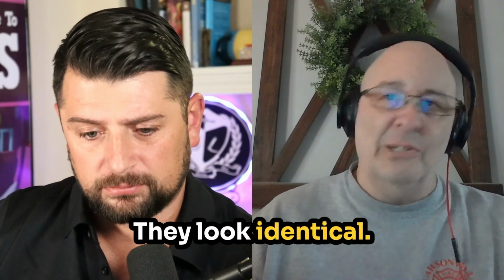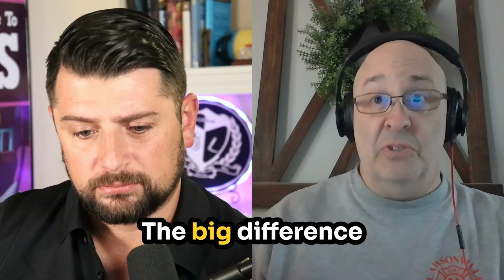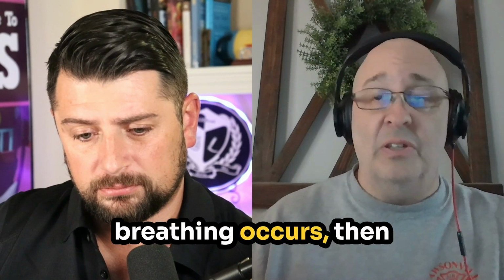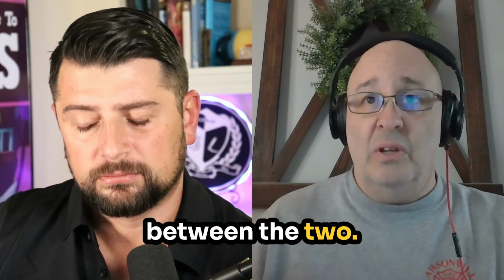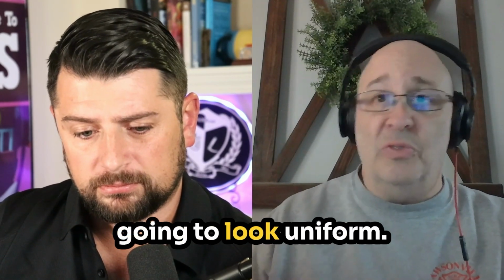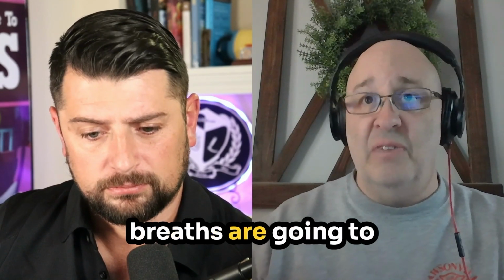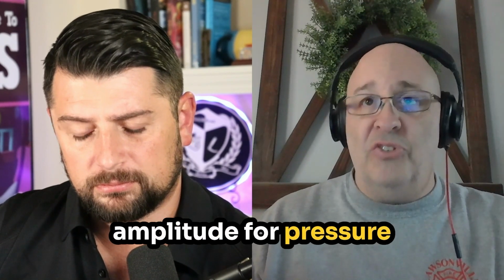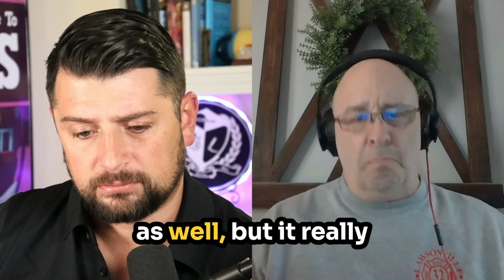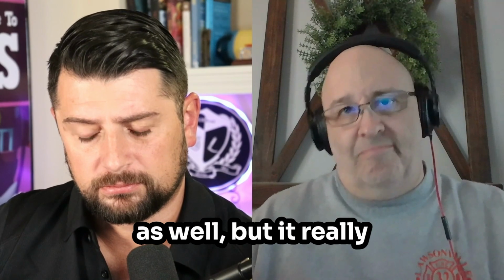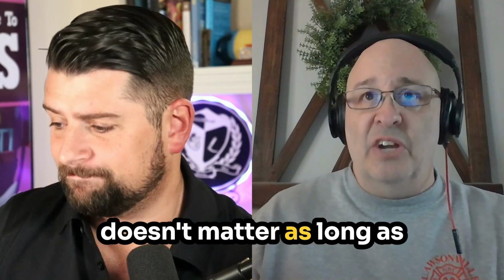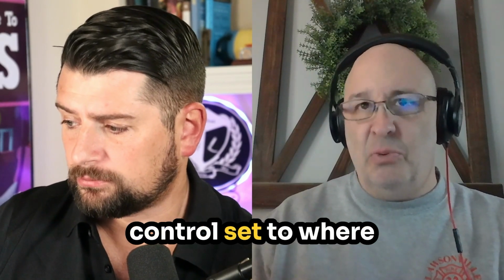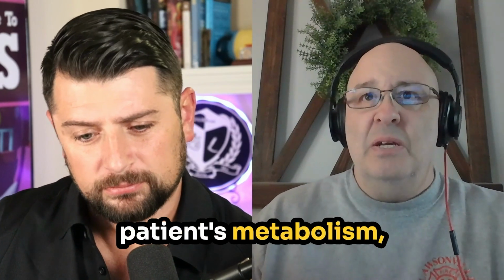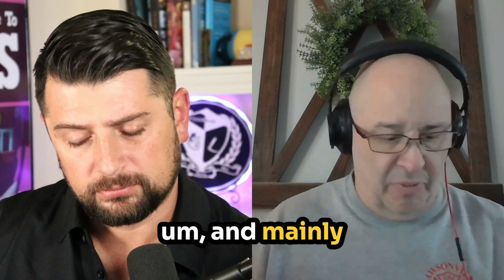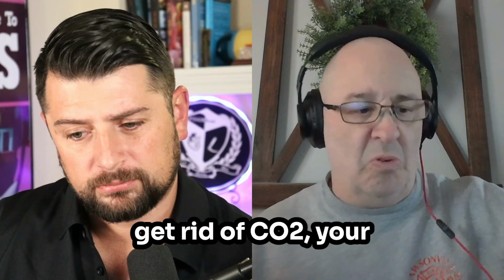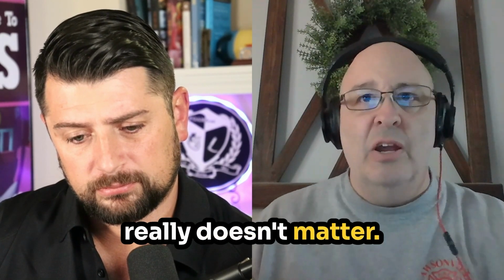They look identical. You can't tell. The big difference is if spontaneous breathing occurs, then you can differentiate between the two. AC, your breaths are all going to look uniform. SIMV, your spontaneous breaths are going to have a different amplitude for pressure, and your flow waveform is going to look different as well. But it really doesn't matter as long as you have your baseline control set to where you can maintain that patient's metabolism and you mainly provide oxygenation, get rid of CO2. Your mode selection there really doesn't matter.